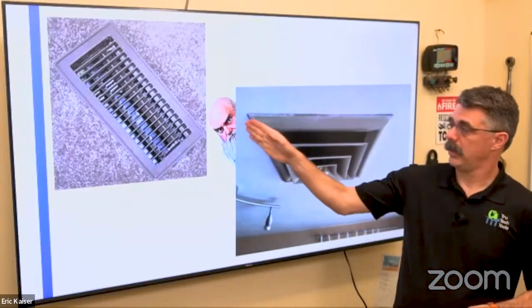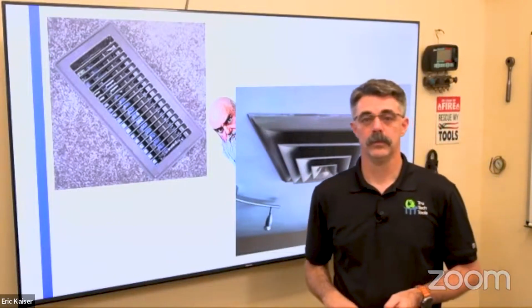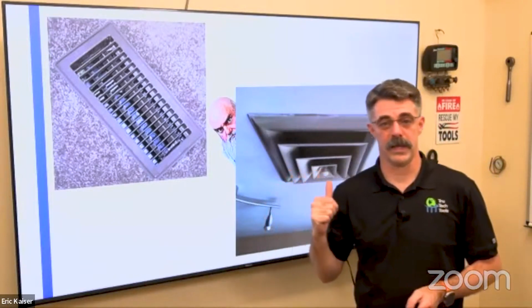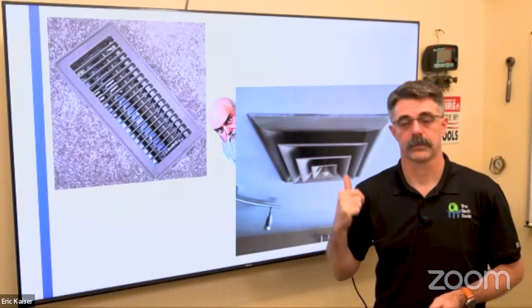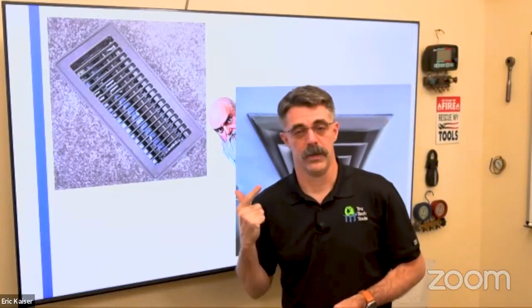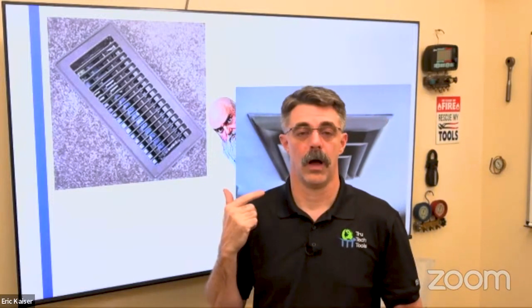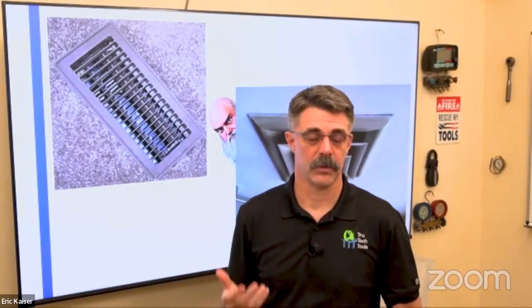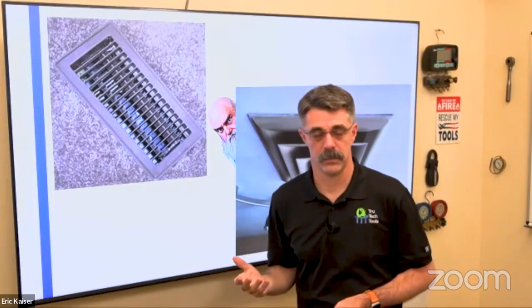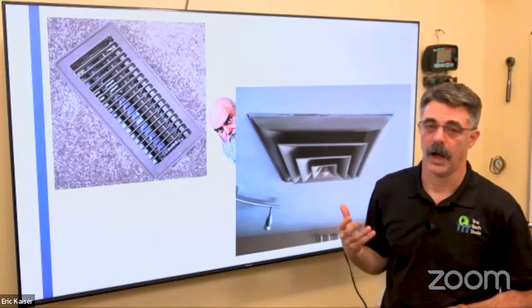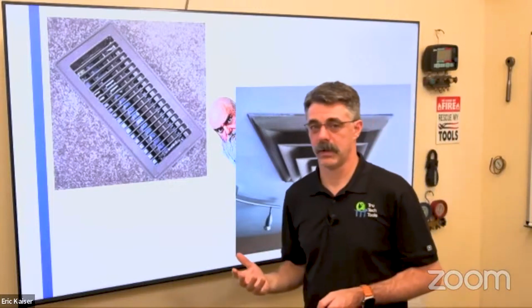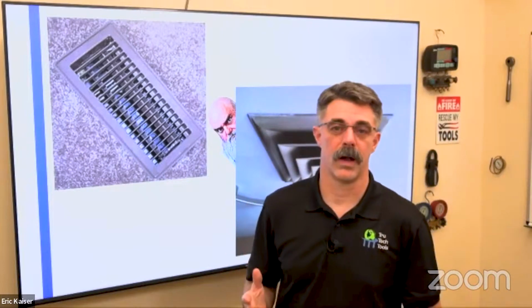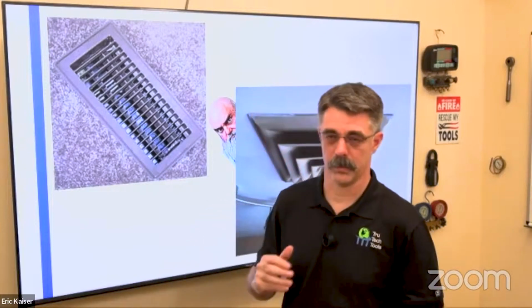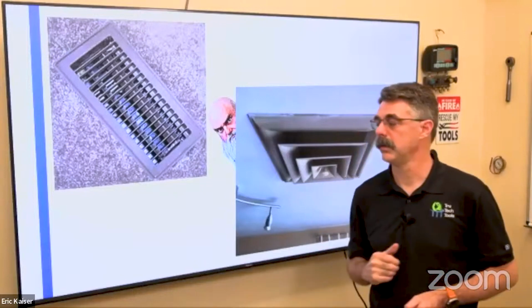What we don't want to do is blow air on people. So we need to make sure our registers are placed properly, number one, and number two, that the registers are of the proper type to put the air where we want it. Now, I have had some customers that love air blowing directly on them. It's very, very rare. You can do that. Be careful. That's what I'm going to say. Be very careful if you do that.